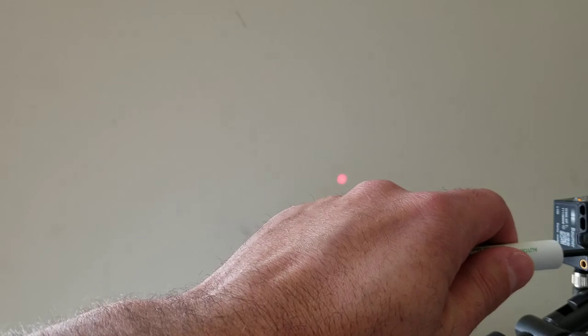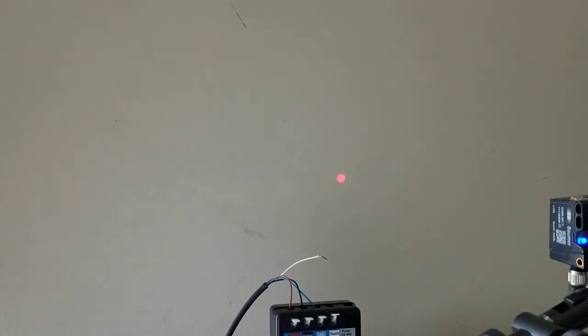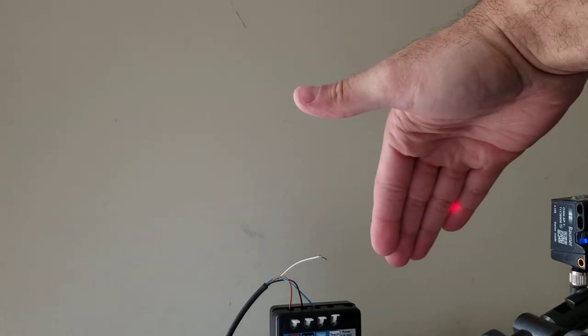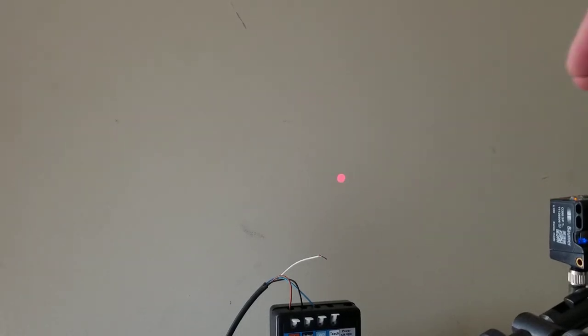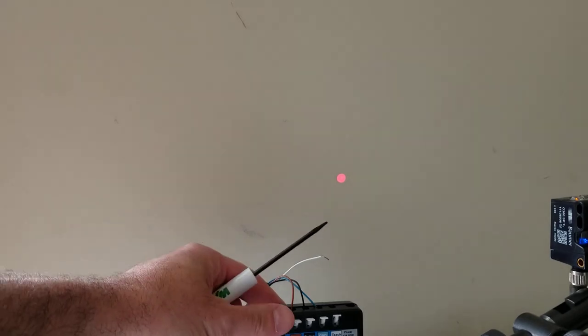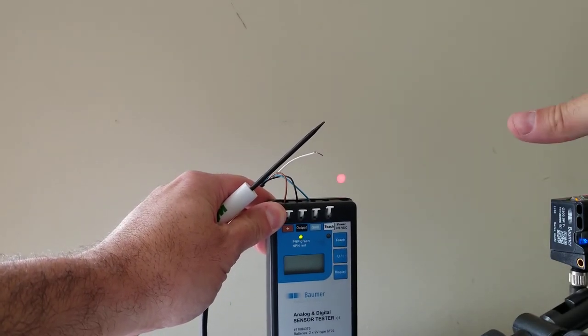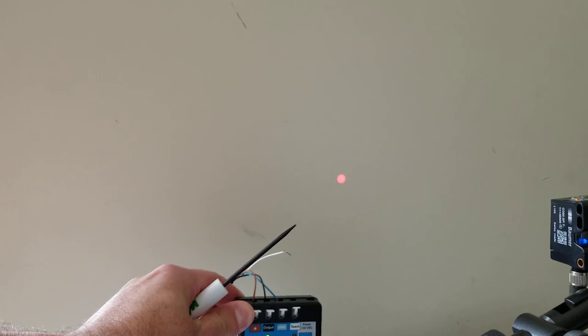I can put this into teach mode and set its reflector to the wall there. And then when it goes through its cycle, now that wall spacing there is the reflector, so you can see on the sensor tester there that the output is changing state.